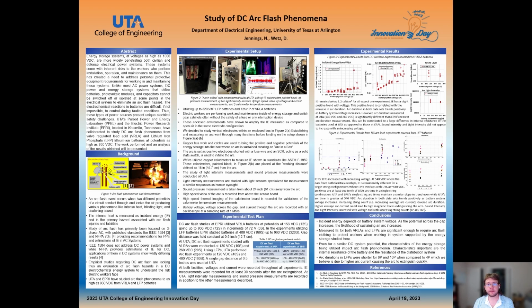Study of arc flash has primarily been focused on AC three-phase systems, producing standards like IEEE 1584 and NFPA 70E. These standards provide estimations of incident energy and recommendations for personal protective equipment in these systems. IEEE 1584 to date does not provide any suggestions or recommendations for DC systems, and NFPA 70E offers few calculations for incident energy in these systems.